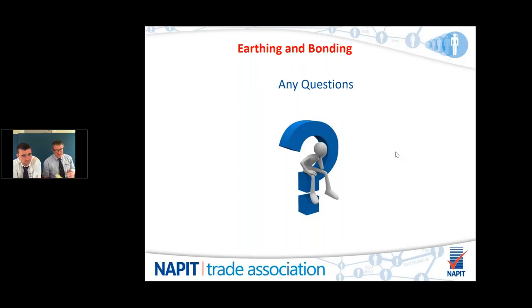Now, adequate is not defined in the regs, I do apologise, but it's not. 6 mil, if you're getting decent ZSs, if the protective devices will operate in the required times, 6 mil to me would go down with a comment on my minor work certificate. Anything else for that? No, I think pretty much covered it.